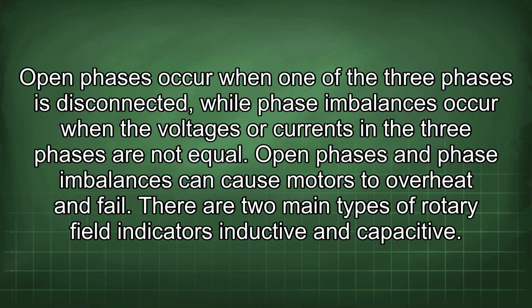Open phases occur when one of the three phases is disconnected, while phase imbalances occur when the voltages or currents in the three phases are not equal. Open phases and phase imbalances can cause motors to overheat and fail. There are two main types of rotary field indicators: inductive and capacitive.